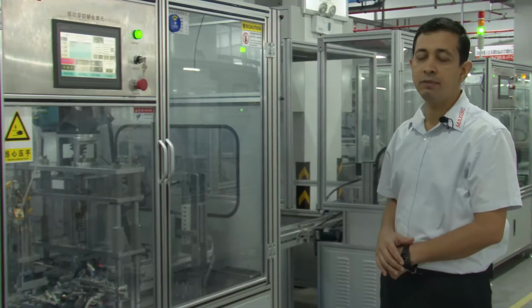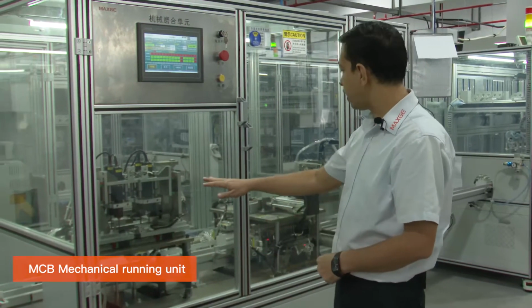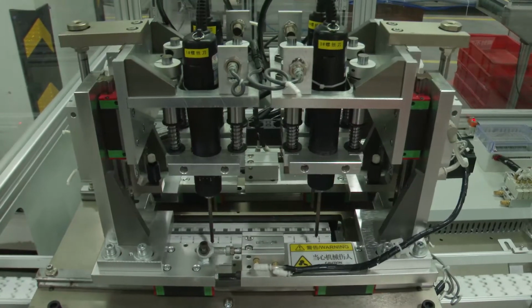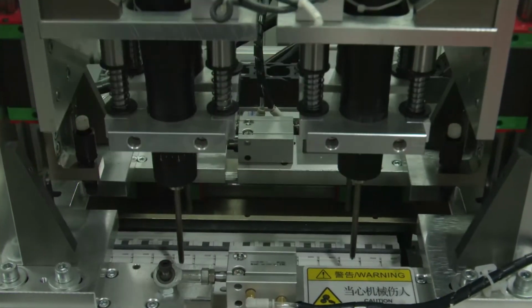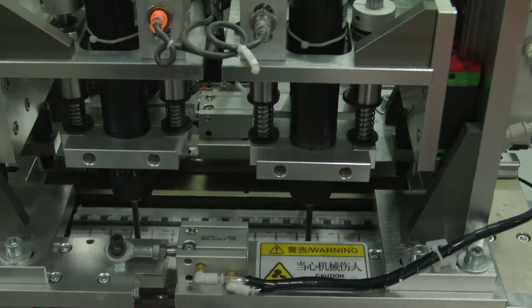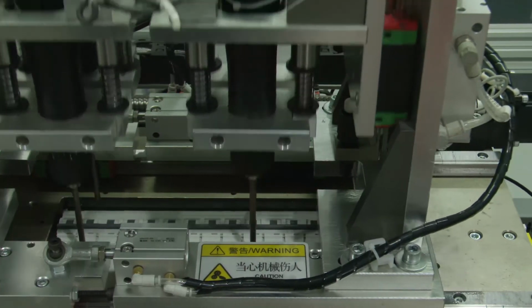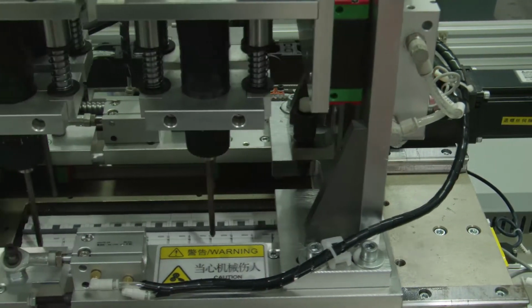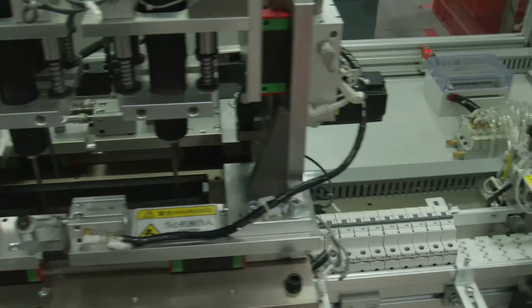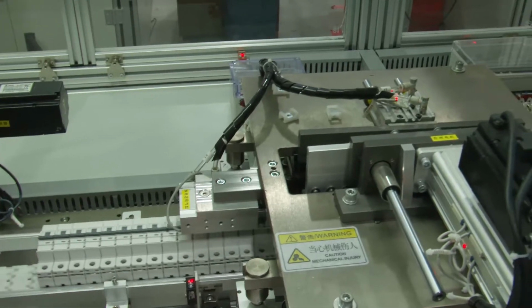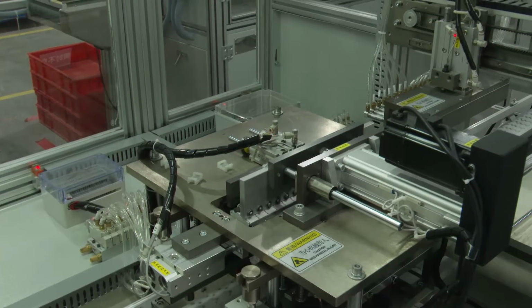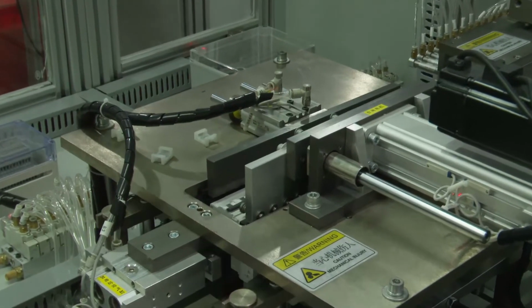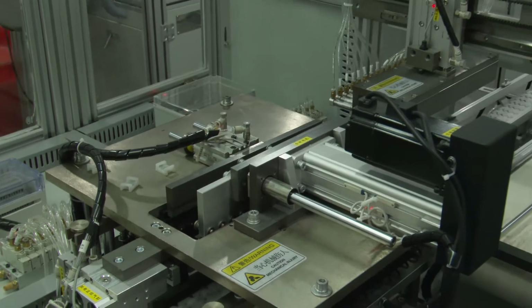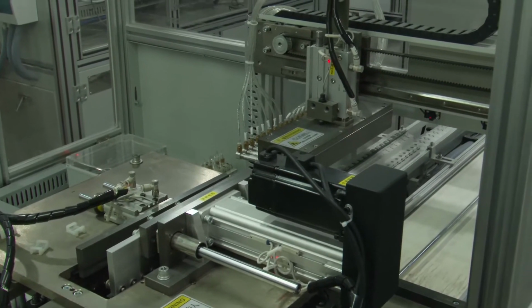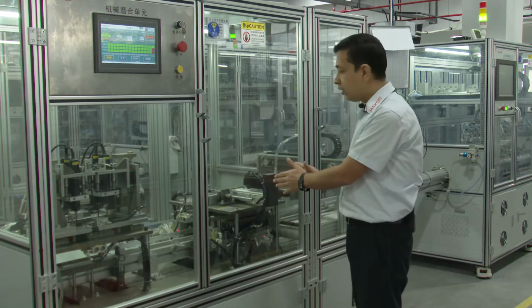Now let's move to the third stage of the testing line. Now we are at the automatic unscrewing station and continuity checking station for the MCB. Why do we need to take out the screws? Because in the later stage we have to check it for the thermal and the magnetic testing, wherein the electrodes are inserted here, and we must ensure the electrodes do not get damaged. So firstly we unscrew the terminal screws, and then we test. The next stage here is continuity checking. First we check the continuity before we do all the other tests.